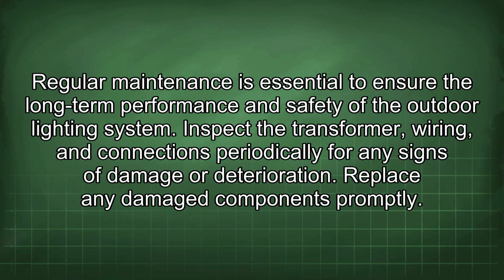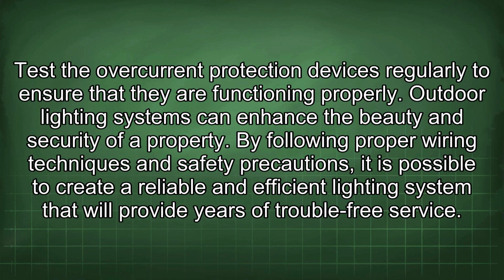Regular maintenance is essential to ensure the long-term performance and safety of the outdoor lighting system. Inspect the transformer, wiring, and connections periodically for any signs of damage or deterioration. Replace any damaged components promptly. Test the overcurrent protection devices regularly to ensure that they are functioning properly.